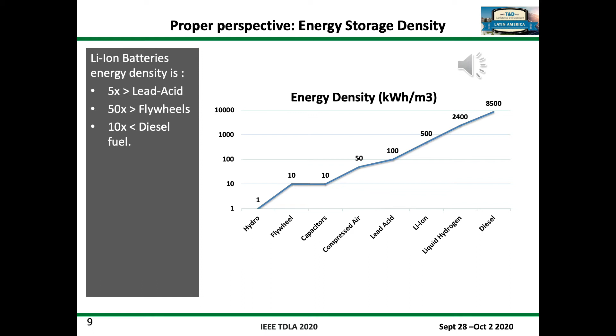To put things in perspective, this slide shows that diesel has the highest energy density from an energy per volume perspective. Capacitors have relatively very low energy density. However, when we look at the perspective of the lithium-ion battery, we can see that the lithium-ion battery's energy density is 5 times higher than the lead-acid batteries, 50 times higher than flywheels, and 10 times lower than diesel fuel or diesel generation. Lithium-ion battery technology is definitely the market leader.